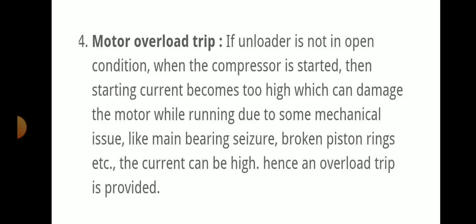Then motor overload trip means if the unloader is not in the open condition when the compressor is started, the starting current becomes too high, which can damage the motor. While running, due to some mechanical issue like main bearing seizure or a broken piston ring, the current can be high, hence an overload trip is provided.